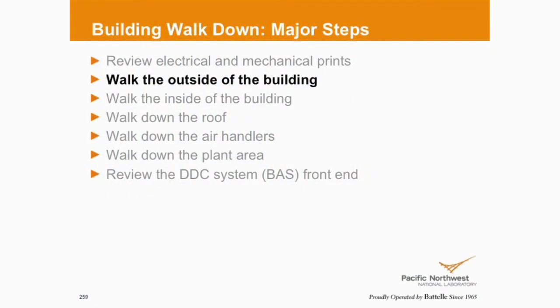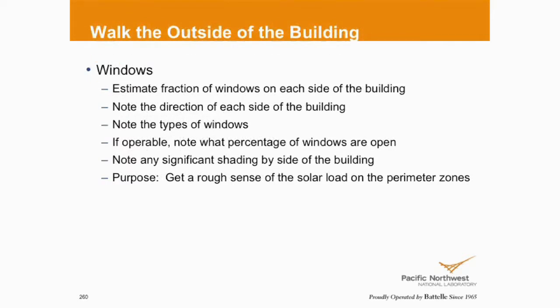Because not everything is on the BAS. Lights is another one. So we want to walk the outside of the building. The only reason why we want to walk the outside of the building is we want to understand, are there challenges with this building, the way it's oriented, solar heat gain, how many windows, what's the window wall ratio. So it's got a lot of glass, beautiful building, but it's got a lot of glass. So now we know it's challenged potentially in the wintertime. Cold winds blowing, it's losing a lot of heat. Summertime, it's gaining a lot of heat.